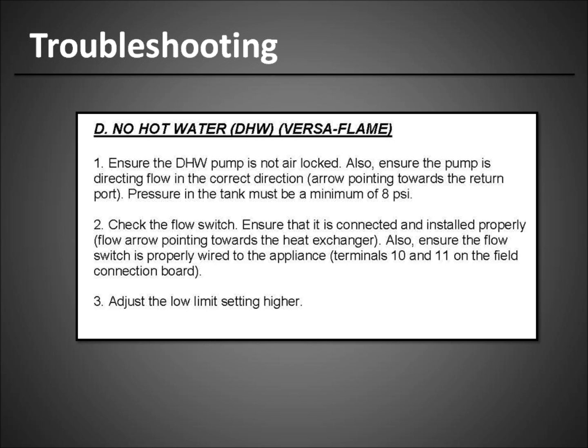Another thing is you want to just check the flow switch. The flow switch is just a simple little plastic paddle that screws in. There's an arrow on it, so it indicates the direction of flow. So we put that in there just to make sure that if there was a hot water problem, they're checking that. And then adjust the low limit setting higher if they're running out of hot water. So one of the things you can do is we've got flexibility to increase the ability to give you more hot water by just bringing that temperature up above the factory minimum set point of 150.